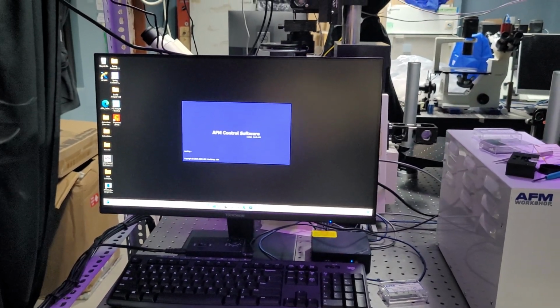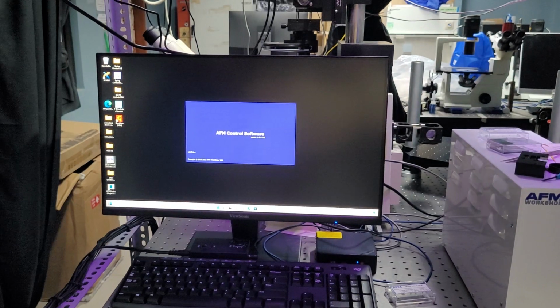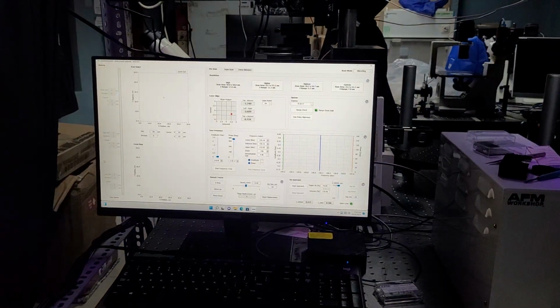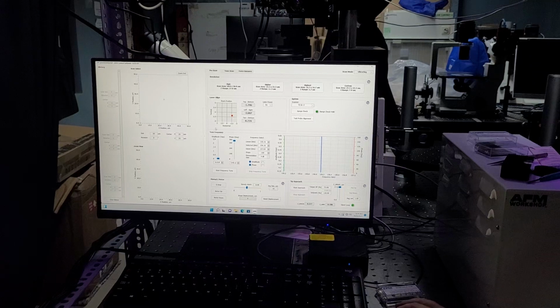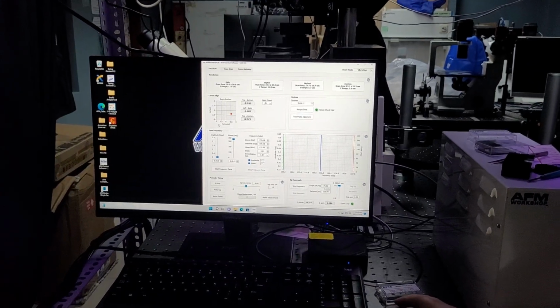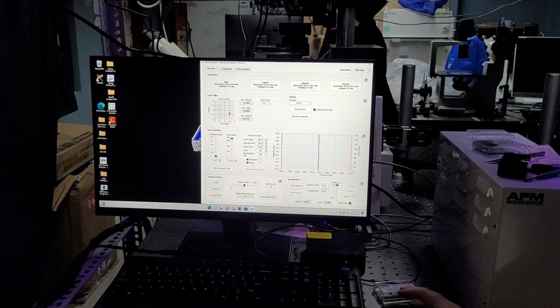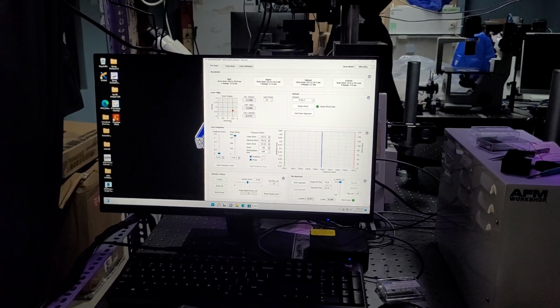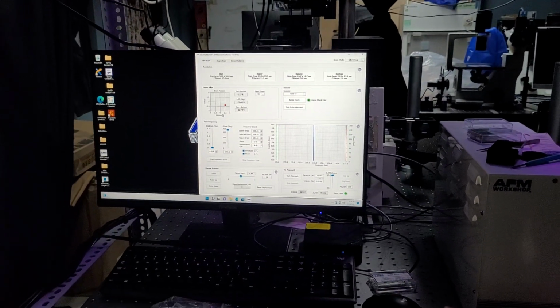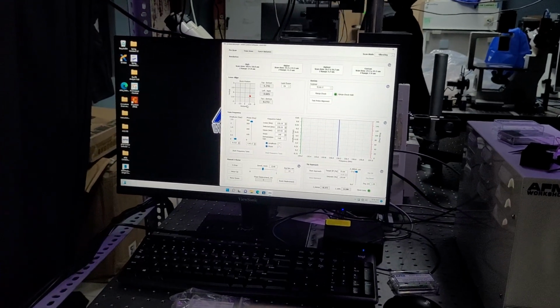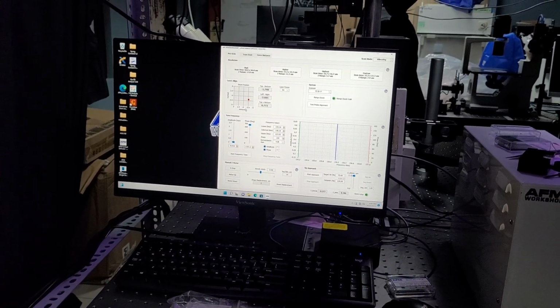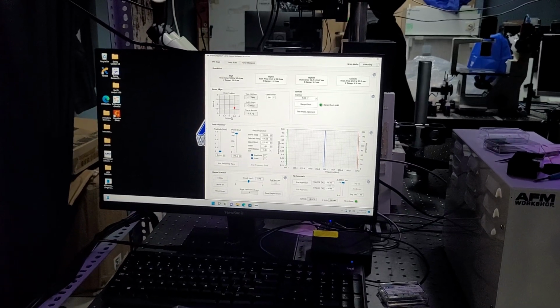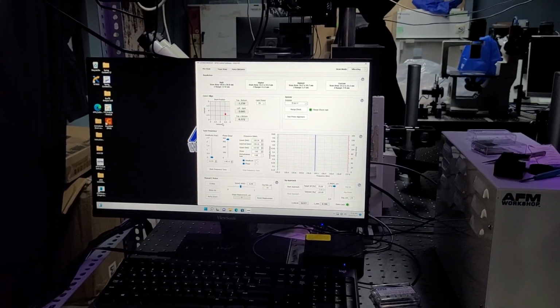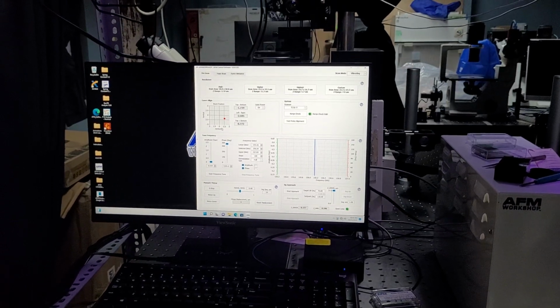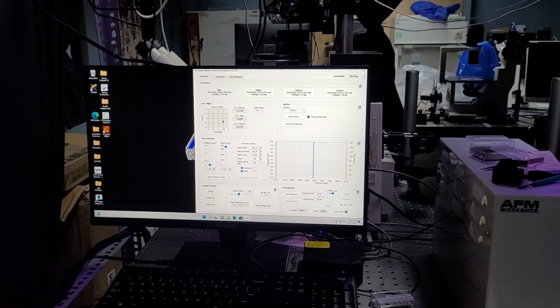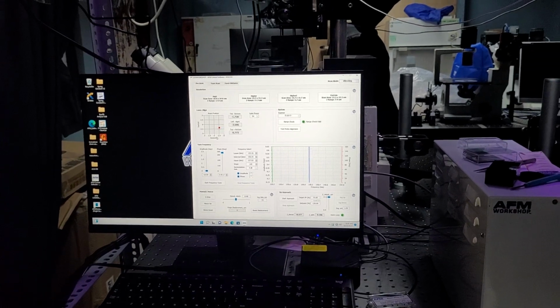A little error message will pop up that will say, well, maybe, never mind, it didn't pop up. From time to time, an error message might pop up that says error, scanner needs to be calibrated. If that pops up, you can ignore it. It's just a bug that pops up every now and then. Like I said before, calibration is at your own discretion. If you want to do it every 3 months, every 6 months, every 12 months, obviously it's your AFM, so you can choose how to maintain and go through that process.